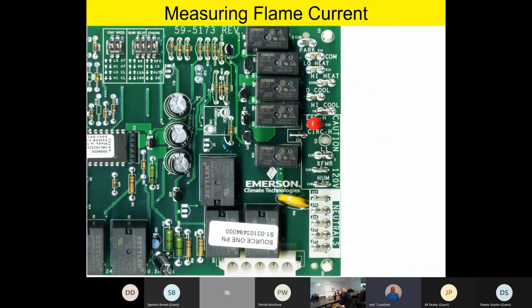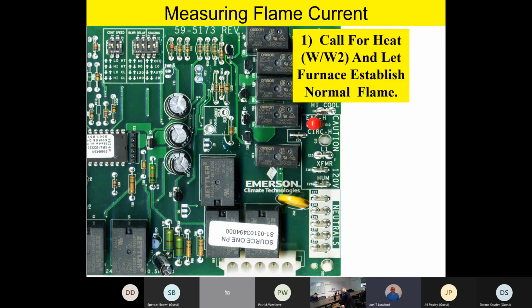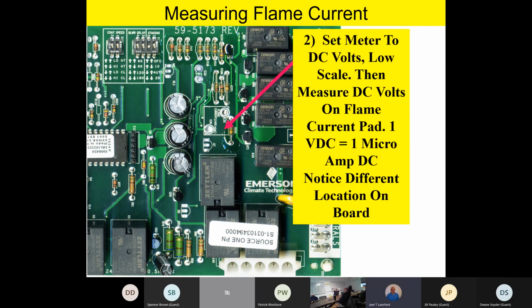So here's a little picture. I cropped the picture of our control board that we're talking about this morning, our TMY. And remember, our flame current pad on this particular control board is kind of in the middle towards the right, around all those relays on the board. So what we're going to do is call for heat. Step number one, call for heat, W or W2, either first or second stage. In other words, it doesn't matter, but call for heat and let the furnace establish a normal flame. Then we're going to set the meter to DC voltage on the lowest scale that we have, and we're going to measure the DC voltage on that flame current.